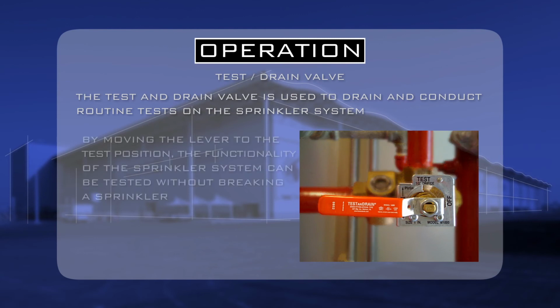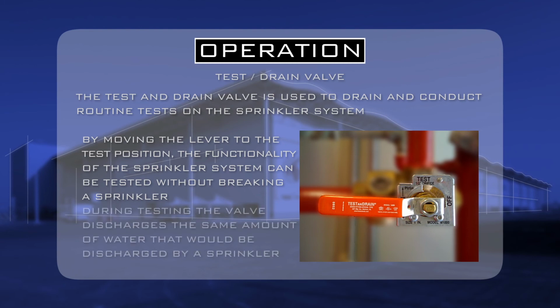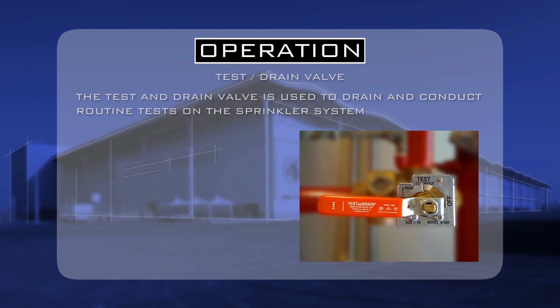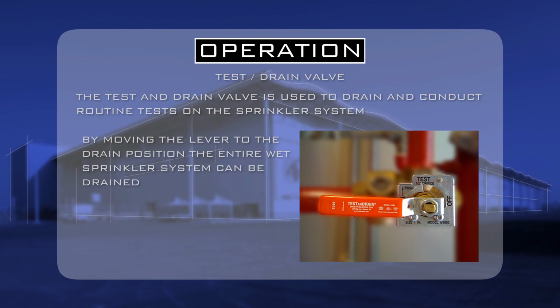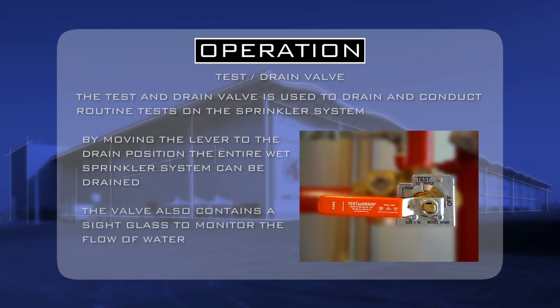system. By moving the lever to the test position, the functionality of the sprinkler system can be tested without breaking a sprinkler. During testing, the valve discharges the same amount of water that would be discharged by a sprinkler. By moving the lever to the drain position, the entire wet sprinkler system can be drained. The valve also contains a sight glass to monitor the flow of water.